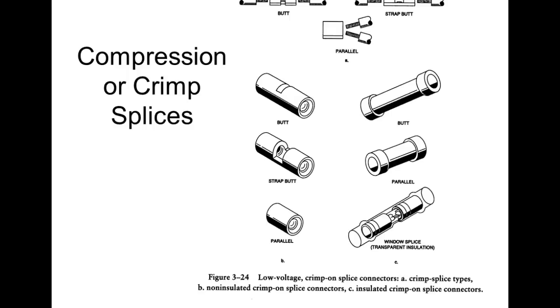And you see a ton of these. Because we don't have to solder them, they're crimped. So what does that mean? Well, that means we're going to put the conductors inside these splices, and then we're going to use the crimp tool to crimp it down onto the conductor and also on the insulation. So normally you have to crimp these twice: you crimp one on the inside for the conductor, and one toward the outside to crimp down on the insulator. Does that make sense?